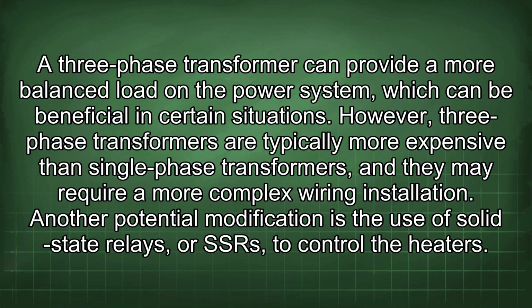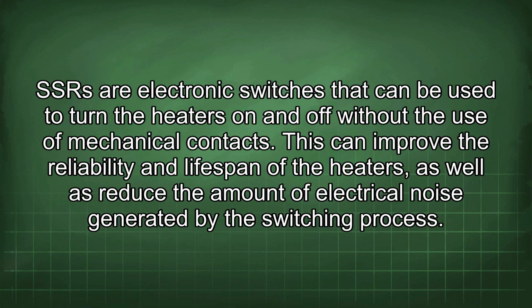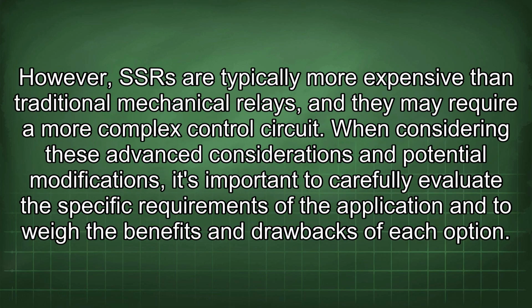Another potential modification is the use of solid-state relays, or SSRs, to control the heaters. SSRs are electronic switches that can be used to turn the heaters on and off without the use of mechanical contacts. This can improve the reliability and lifespan of the heaters, as well as reduce the amount of electrical noise generated by the switching process. However, SSRs are typically more expensive than traditional mechanical relays, and they may require a more complex control circuit.